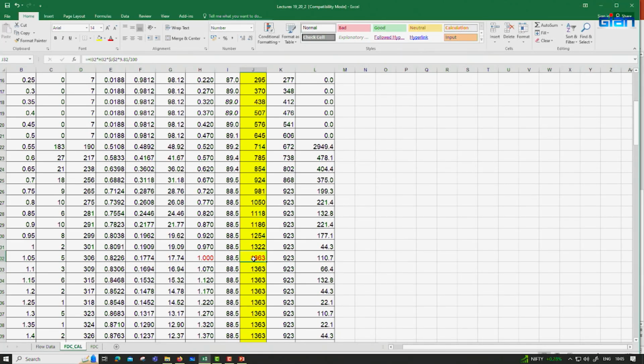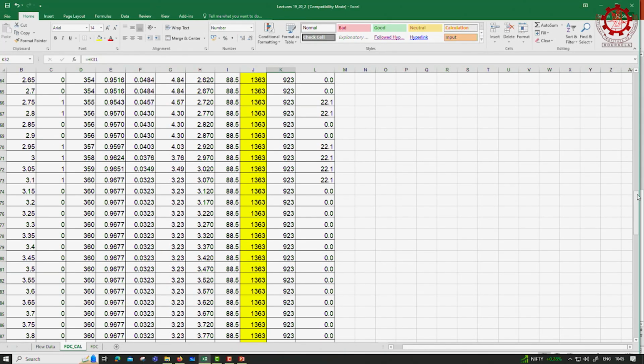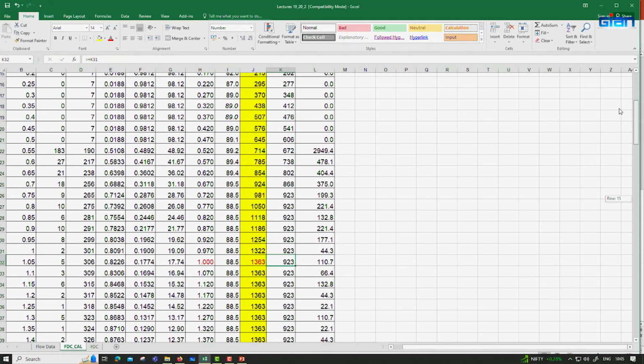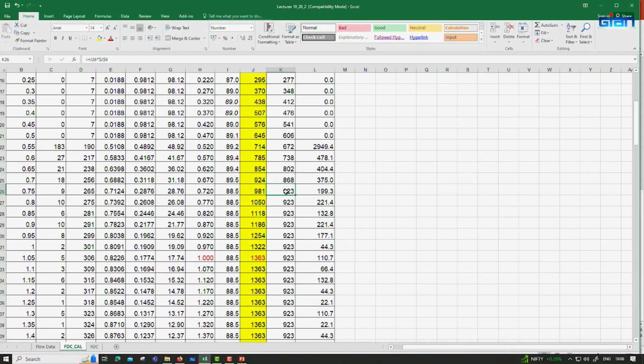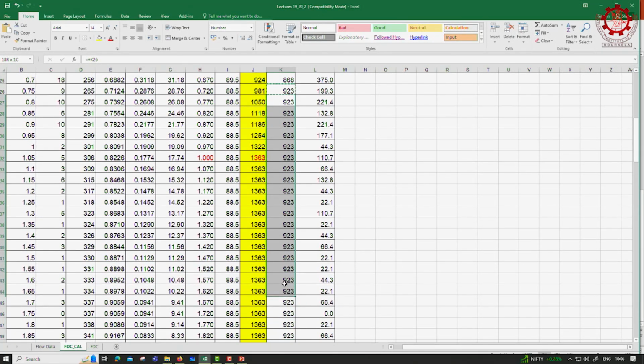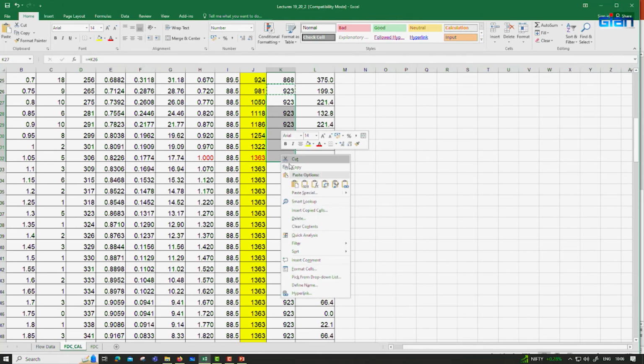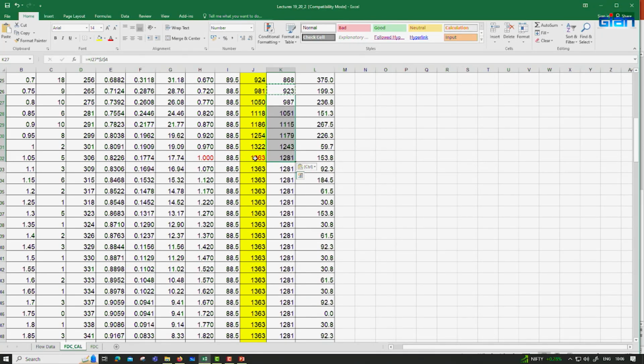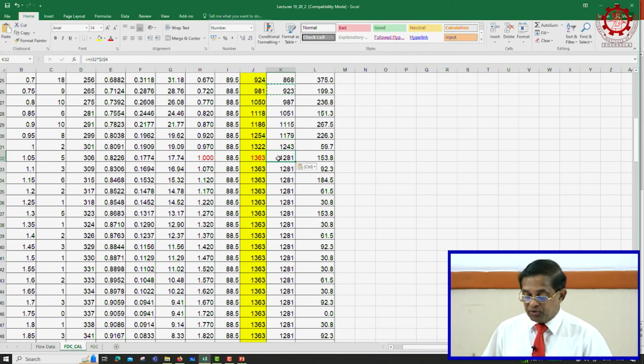When you buy the equipment you will buy the nearest standard component, turbine or transformer, whatever, right. But for the calculation we will use the actual value, 1363, right. So, you can see the plant output when it is running on full is this column, I have to modify it a little bit. Previously I had frozen it somewhere there. Right. So, when 1363 is the turbine output, plant output is 1363 into 0.94, which is 1281, right. I hope up to that point it is clear, right.